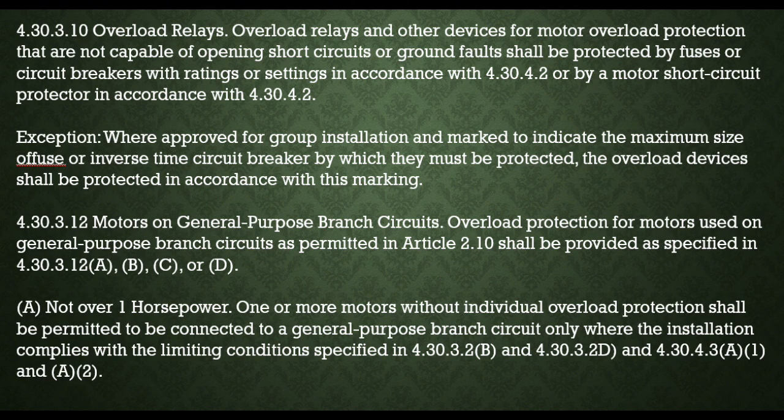And for motors on general purpose branch circuits, overload protection is detailed in 4.30.3.12A, B, C, and D. Motors 1 horsepower or less without individual overload protection can connect to a general purpose circuit if it meets conditions in 4.30.3.2B and 4.30.3.2D and 4.30.4.3A1 and A2.